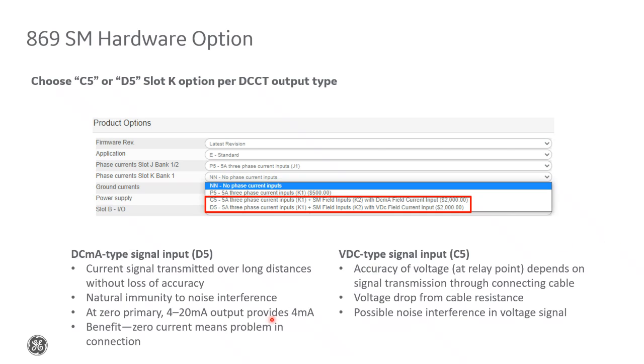The selection of what type of output signal that you would choose depends on your installation requirements. Typically, if the CT leads only need to be run a short distance, then the volts DC signal might be okay. Otherwise, it might be susceptible to voltage drop from the cable resistance and noise interference, both of which can affect the accuracy of the signal. If possible, we usually suggest to use a DC milliamp signal since it's not as affected by the cabling or the noise. And it also provides an added bonus for troubleshooting.